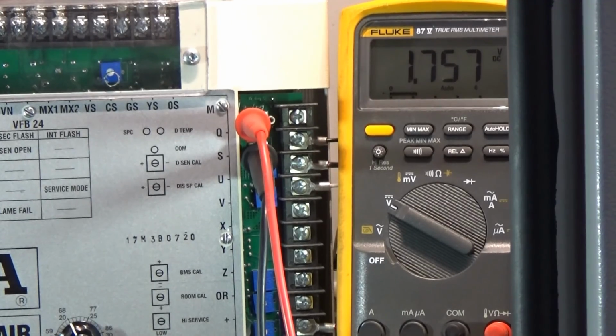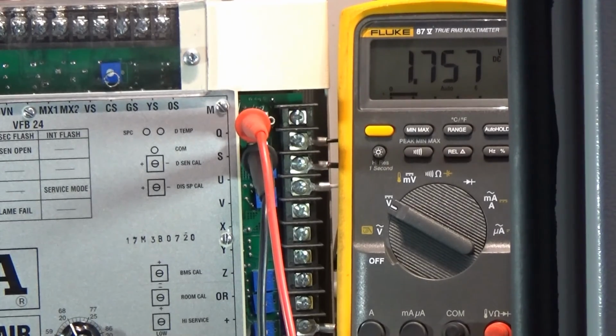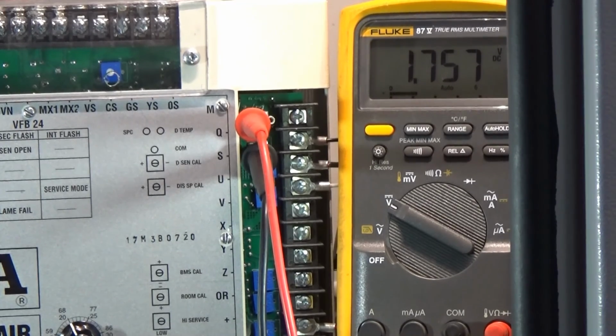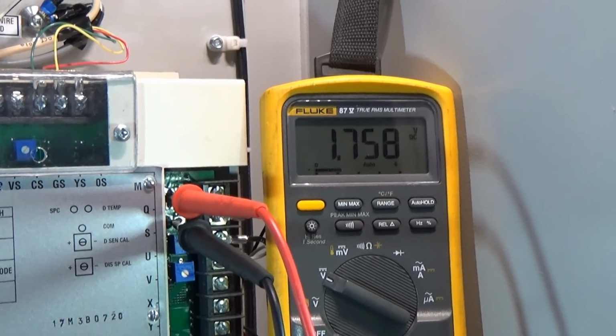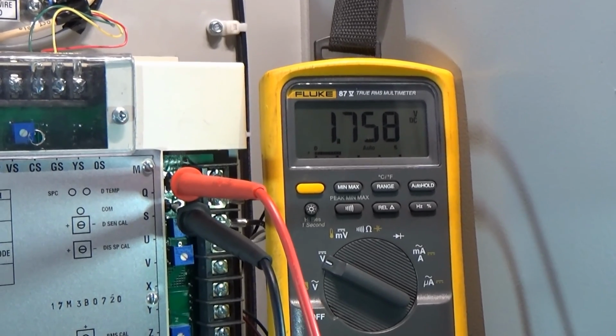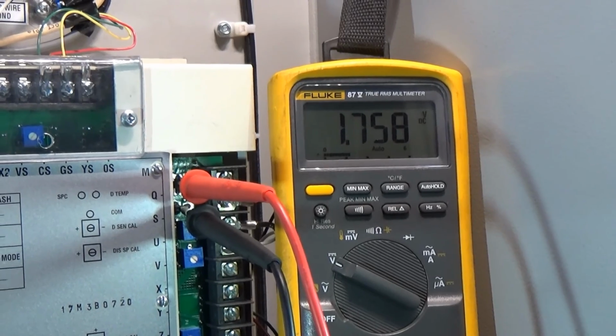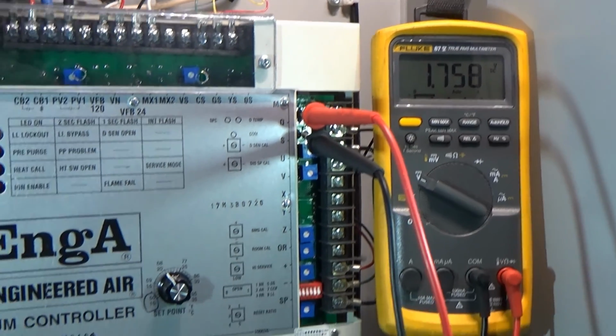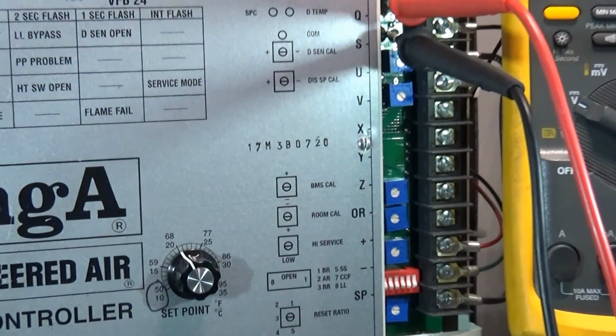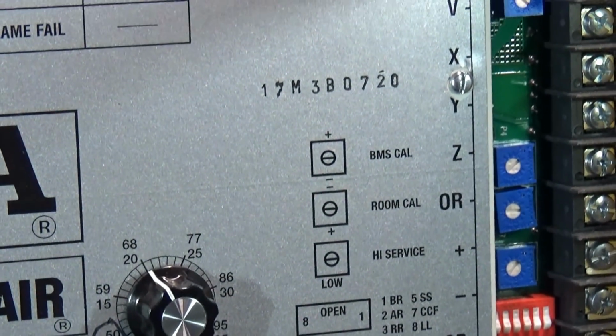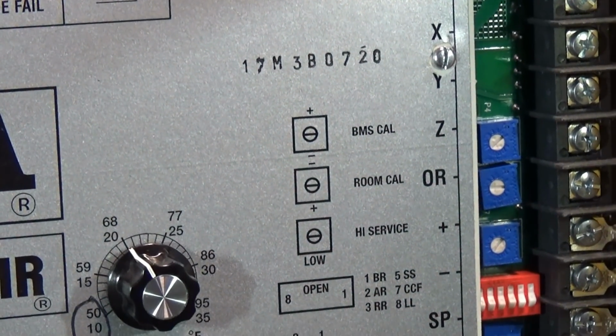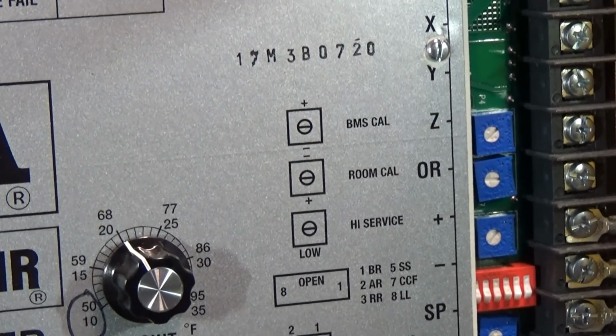1 volt DC is equal to 10 degrees Celsius. On this meter, you can see 1.7 volts DC, or 17 degrees Celsius. The readout on your meter should match your setpoint dial on the face of the controller. In this case, it does not match, and the setpoint will have to be calibrated.